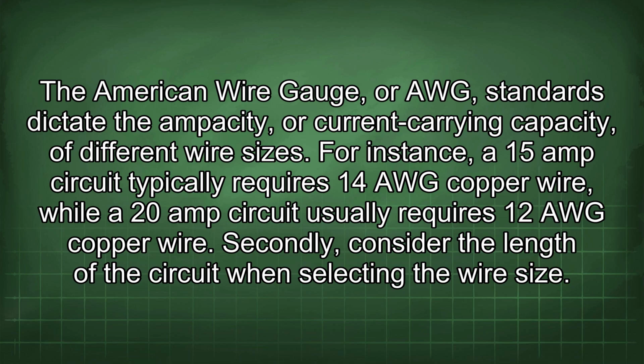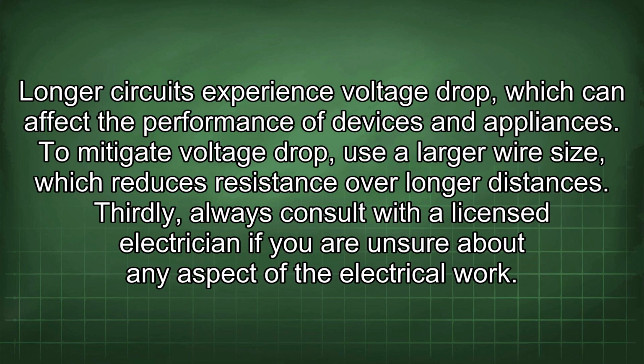For instance, a 15 amp circuit typically requires 14 AWG copper wire, while a 20 amp circuit usually requires 12 AWG copper wire. Secondly, consider the length of the circuit when selecting the wire size. Longer circuits experience voltage drop, which can affect the performance of devices and appliances. To mitigate voltage drop, use a larger wire size, which reduces resistance over longer distances.